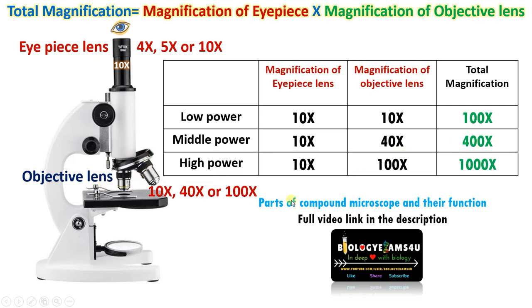Then rotate it to high power. At high power we are using the same eyepiece lens, which is 10x, and the high power objective has a magnification of 100x. Therefore total magnification will be 10x × 100x = 1000x. That's why the maximum magnification of a compound microscope is often given as 1000x — meaning the object appears one thousand times larger than the actual object.